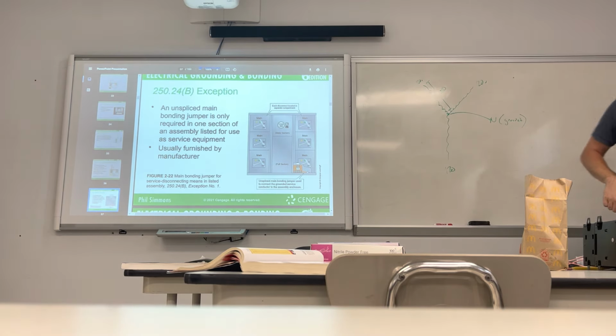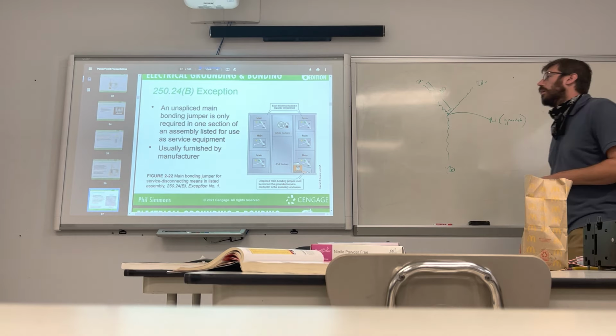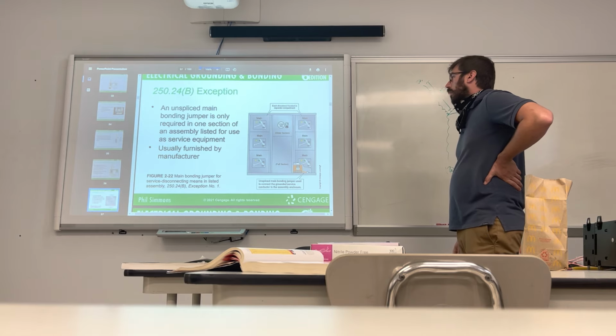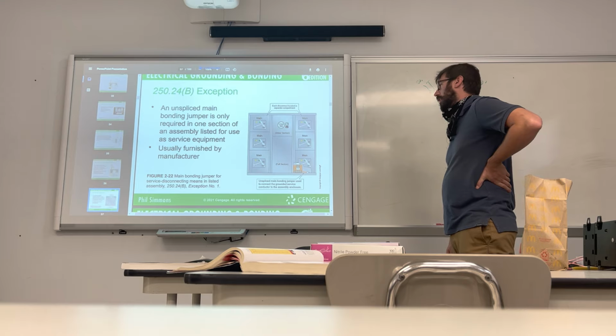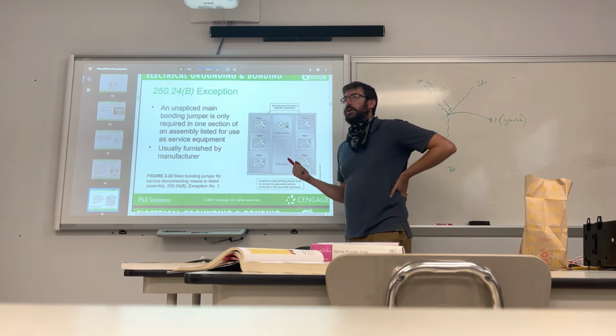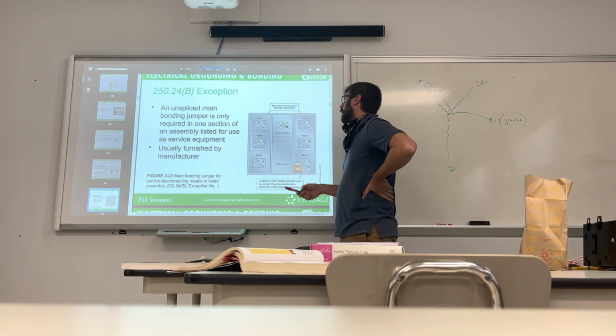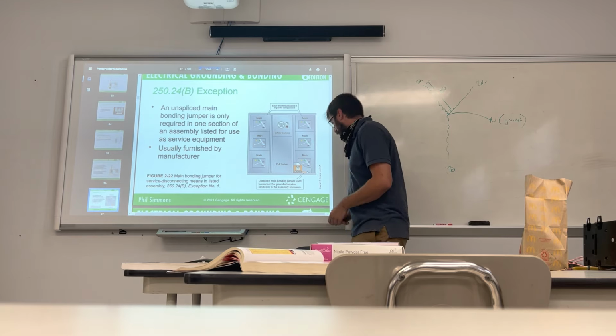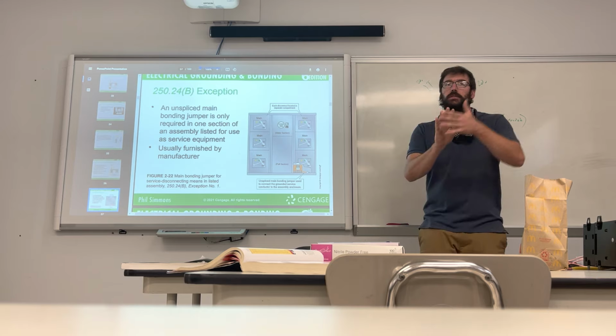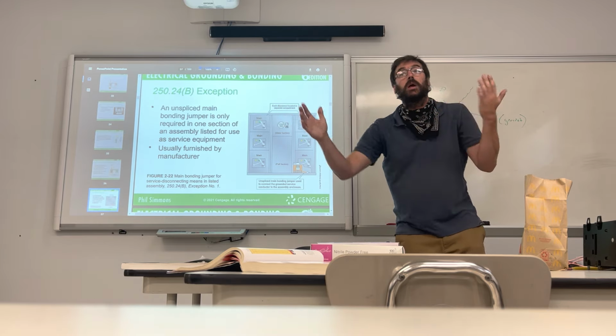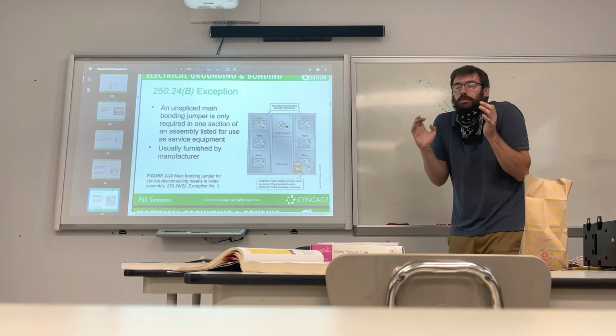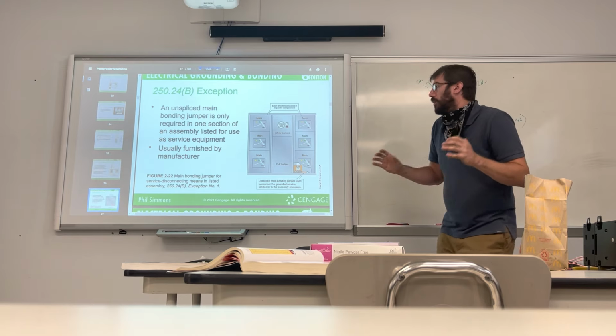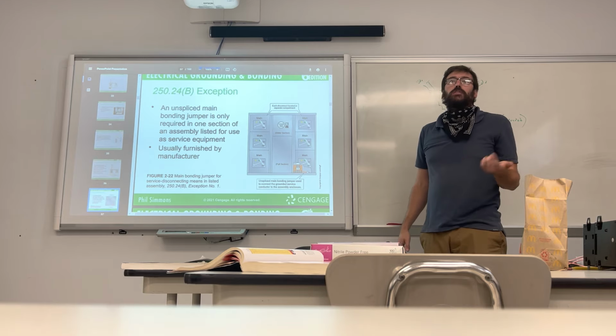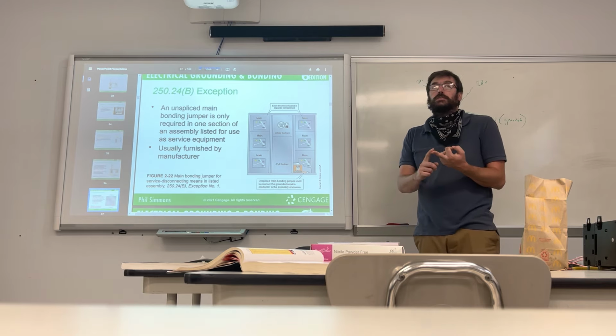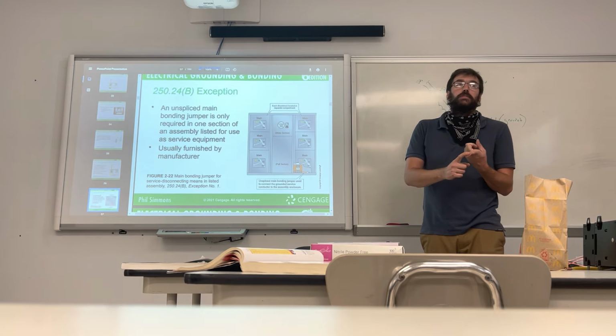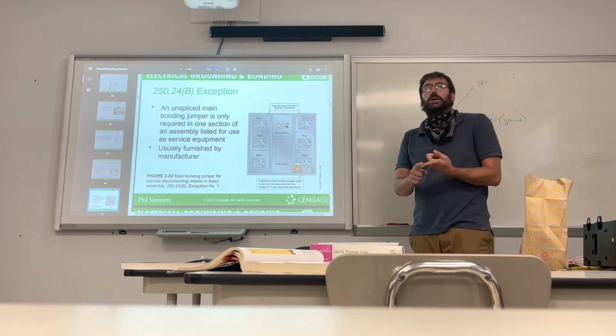Exception to 250.24(B): an unspliced main bonding jumper is only required in one section of any assembly listed for use as service equipment, usually furnished by a manufacturer. Yeah, because this is a big switchboard, right? Or they call it switchgear. Each one of these mains is isolated from one another in its own pocket. You might think the main is just a panel board with some wires behind it connected to a service bar, but in reality that main is almost like a bulletproof, bomb-proof little cabinet compartment within the big cabinet. If there's an arc flash and an arc blast, we know copper can expand at 64,000 times its original size, and temperatures can reach 35,000 degrees Fahrenheit, which is higher than the surface of the sun. So there's a lot of danger associated with that.